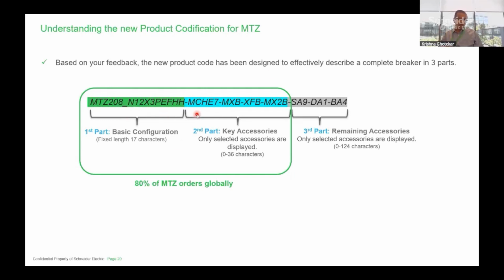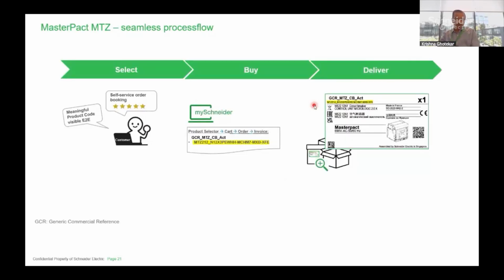Plus, if you add on motor, coil, like MCH is motor, MX is closing opening coil, XF is closing coil, MN for under voltage coil, and so on, the part number can be developed. Don't worry, I will show you one Excel format in terms of the nomenclature of the part number for easy reference, and also we will check, I think if we have time, we will quickly go through the product selector part also. So this one you can directly have from the product selector, the part number, which comes with that bill of material, and the same is displayed on the packaging label or the invoice.